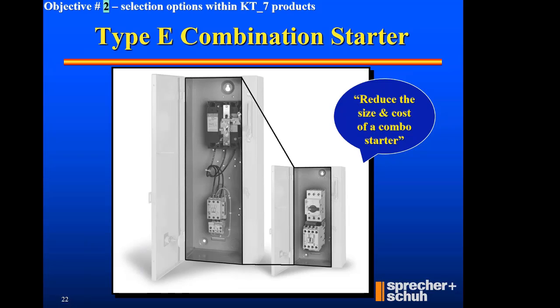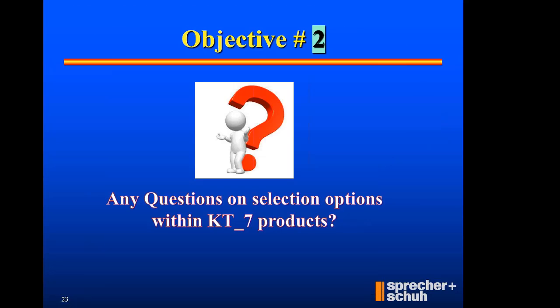So visually, what are we talking about here? I keep talking about a traditional 3-component starter versus a Type E 2-component starter. Visually, we're talking about reducing the physical size of a combination starter. When you reduce the size, you're reducing all that metal of the enclosure and the cost of the enclosure. And when I go from a 3-component combo starter down to 2-component, I'm reducing the number of components and the cost of the components. So it hits you in the face that I can reduce the physical size and the cost of a combo starter, dependent on whether I can keep it at 45 amps and under. I'm going to hesitate on the offering of KTA7, KTA, KTB, KTC.